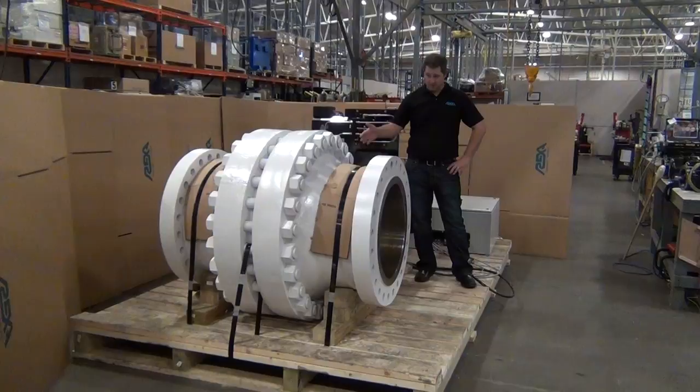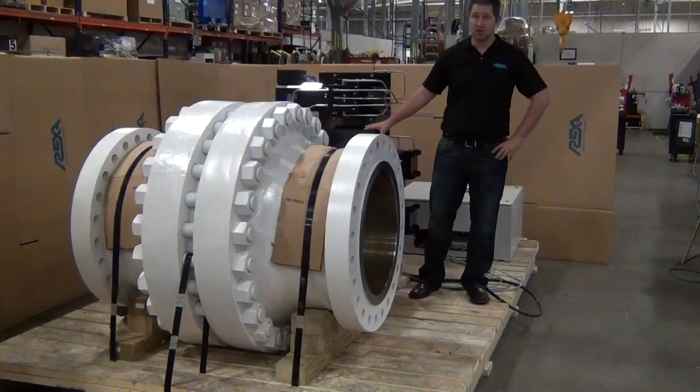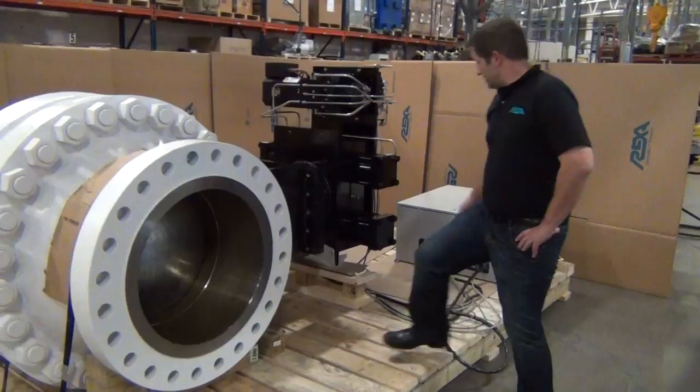Here at Koso America, REXA electro-hydraulic Actuators. We're looking at a 24-inch ball valve, 600 ANSI class, for a liquid pipeline in the U.S., with a REXA self-contained electro-hydraulic Actuator. The actuator is rated for 600,000 inch-pounds of torque, or 50,000 foot-pounds of torque, and it is 100% duty cycle.